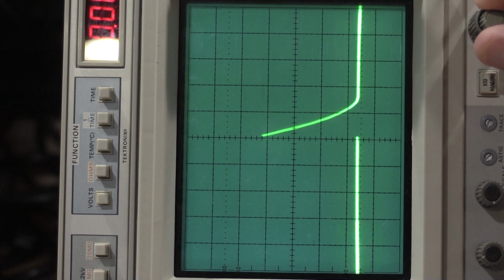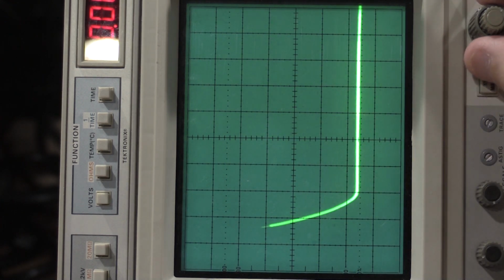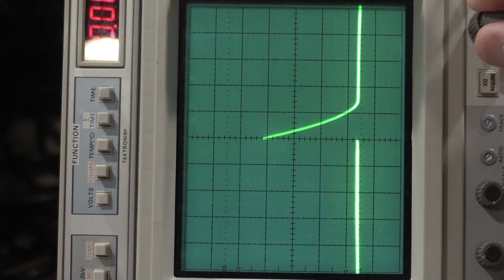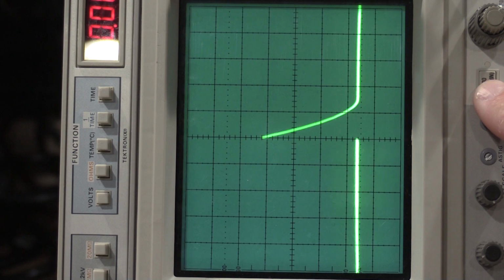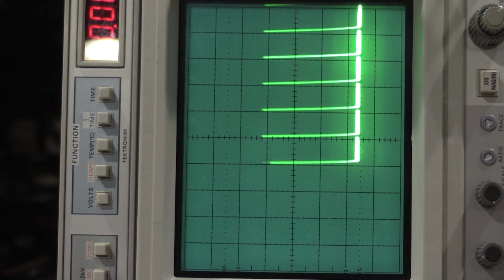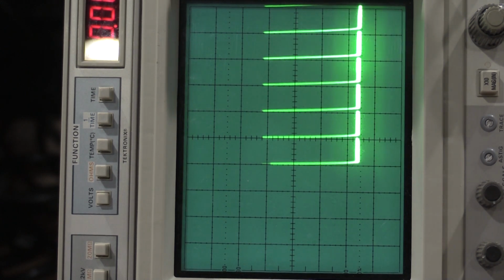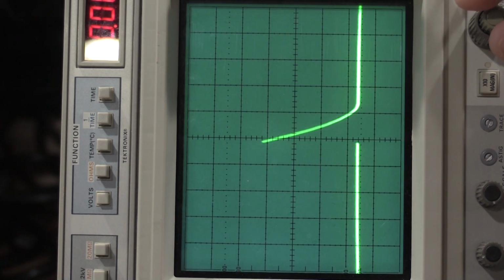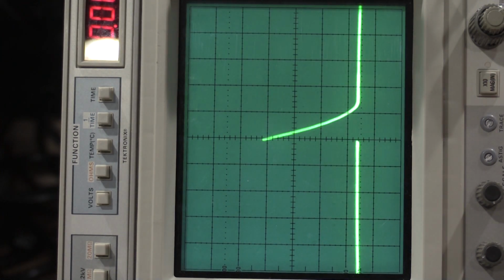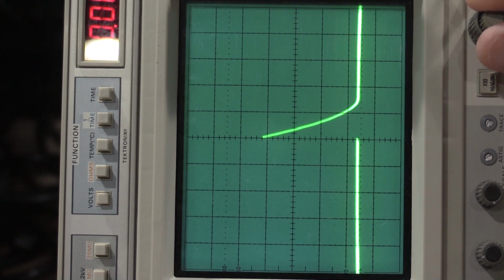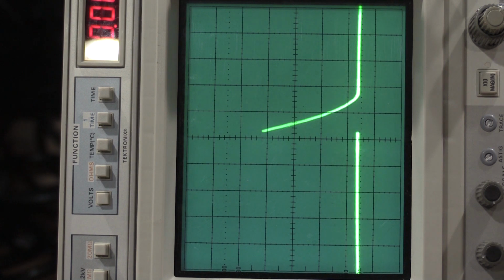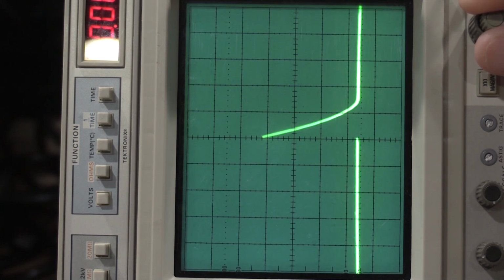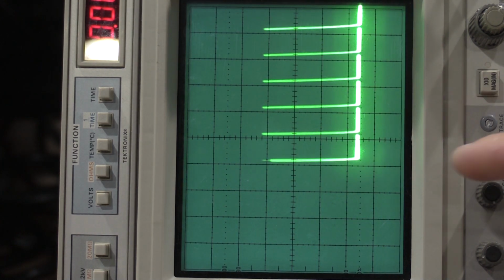And we have to do this a few times because there's interactions. So we pull the, so we're on the second time mark. And we disable the 10x mag. And then we bring the second time mark back to the center. Like so. Do it again. The movement is a little bit of thermal effect in the transistors. You're seeing thermal settling. So this is also one of the reasons why I need to make that calibration card for the 7854, because it's the thermal channel balance. That's why I'm giving it a second, because it'll come back.